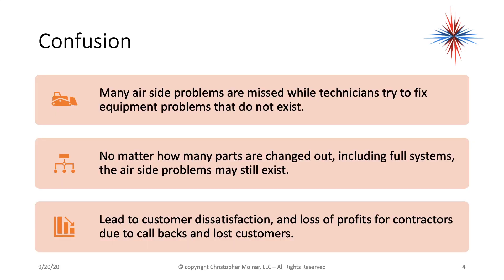Many air side problems are missed while technicians try to fix equipment problems that do not exist. By equipment I mean the air handler, the furnace, or the condenser. But a lot of times these problems are air side, which would include all the duct work and everything that occurs within duct work, as well as pressures. No matter how many parts are changed out, including full systems, the air side problems may still exist because the duct work is not always replaced with the system. This can lead to customer dissatisfaction, loss of profits for contractors due to callbacks, and lost customers. So air side diagnosis can affect your business.